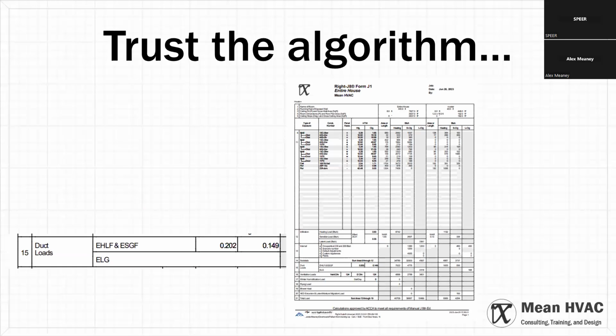But if I'm above, say, the 30% mark—that's a reach, but in some of the hotter areas in South Texas, code minimum with a trunk and branch system might put you there. The big things you'll notice: if you've got a duct system in the crawl space and there's nothing in the attic, and it's 20%-plus here, 0.20 and higher, that's a red flag.